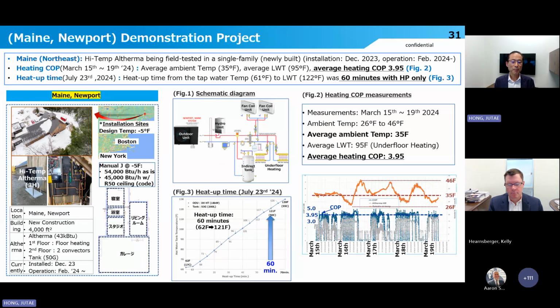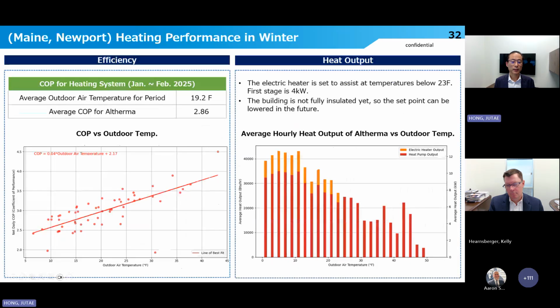ambient temperature. Also, we measured how long we need to wait until we have full hot water with a 50-gallon tank. We filled up the tank with tap water at 62 degrees, and heated up the tank with heat pump operation only in July last year. It takes 60 minutes to heat up the tank with 120-degree hot water.